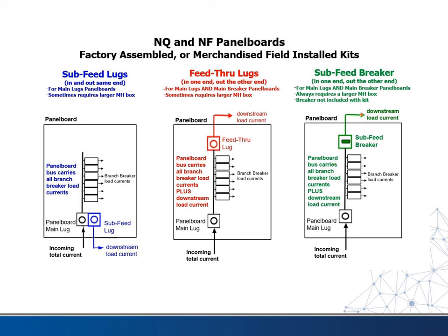Now, if we might have a smaller panel downstream, then we can use what's called a sub-feed breaker. So here, same thing, we come in with our conductors, hit this lug, goes through the bus, feeds these breakers, and then we put more lugs in a breaker, or maybe we might just insert a breaker if it'll fit in the panel. You have to check the manufacturer. You can set a sub-feed breaker, and then we come off here with something smaller.